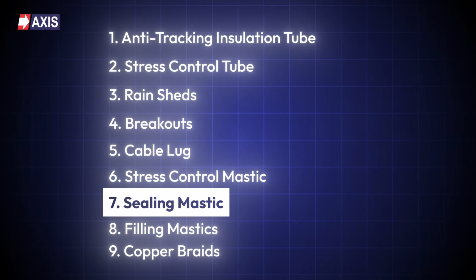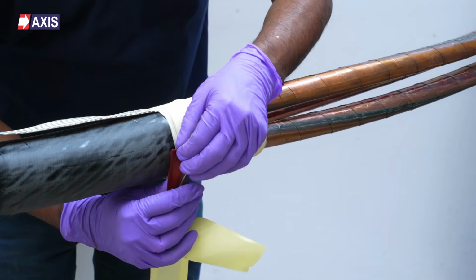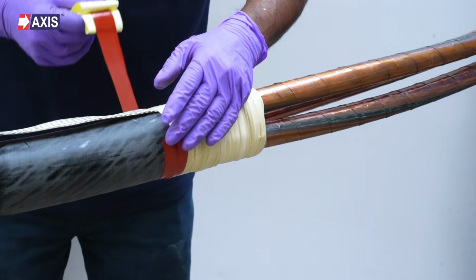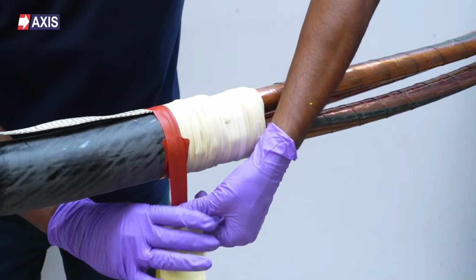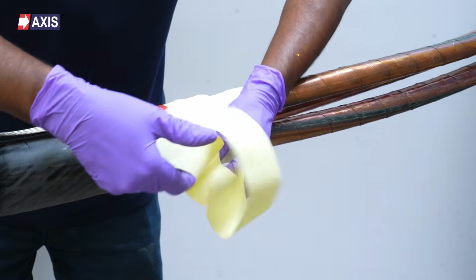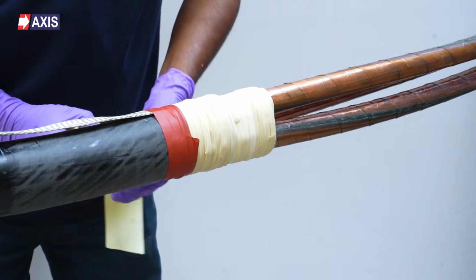Seventhly, the sealing mastic. These mastics are used to block gaps and seal interfaces within the termination. They prevent the ingress of moisture, dust, and contaminants that can compromise insulation performance over time. And by creating a continuous and sealed profile, sealing mastics help maintain electrical integrity and protect your termination from environmental degradation.